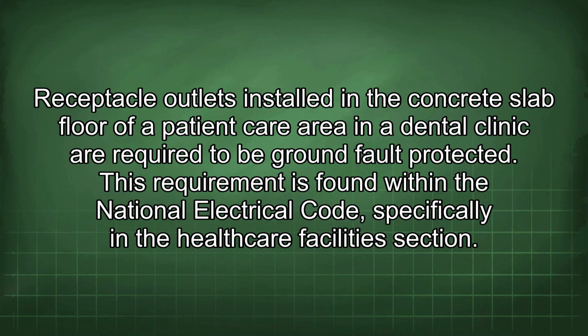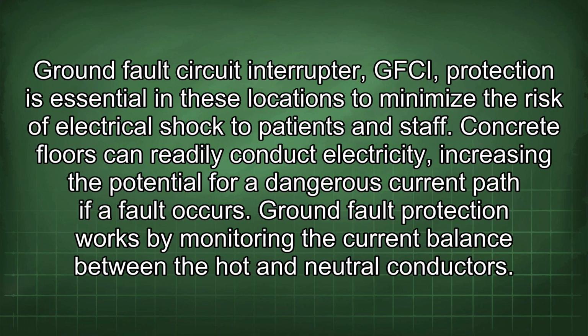Receptacle outlets installed in the concrete slab floor of a patient care area in a dental clinic are required to be ground fault protected. This requirement is found within the National Electrical Code, specifically in the Healthcare Facilities section. Ground fault circuit interrupter (GFCI) protection is essential in these locations to minimize the risk of electrical shock to patients and staff. Concrete floors can readily conduct electricity, increasing the potential for a dangerous current path if a fault occurs.